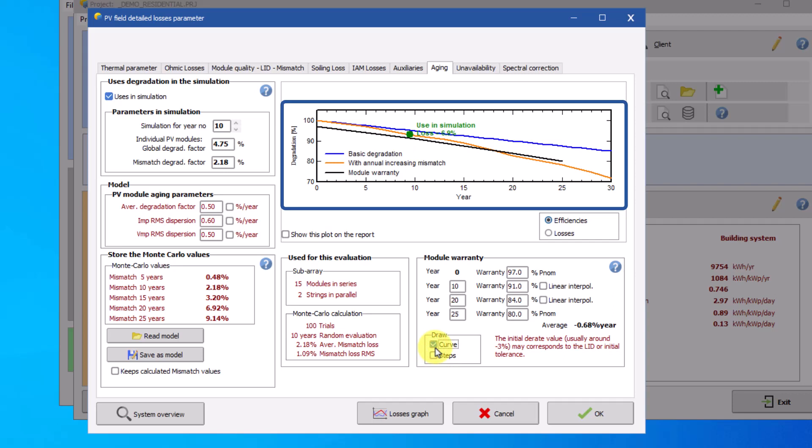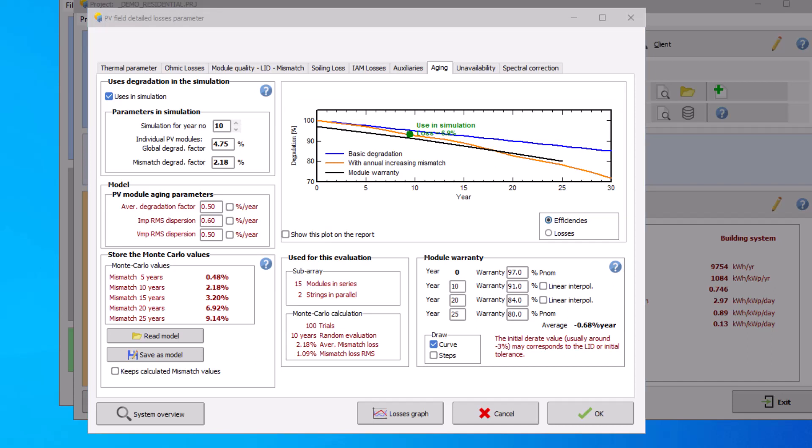The graph also illustrates a relative degradation with respect to a new PV module over a number of years. The blue line represents the global degradation of the PV module. This should translate to the decrease of power output of a PV module over time. The orange line is the degradation taken into account the distribution of IMP and VMP. This distribution increases with time and causes an increase in mismatch within strings. The green circle on the curve represents the total aging loss for the year of simulation.